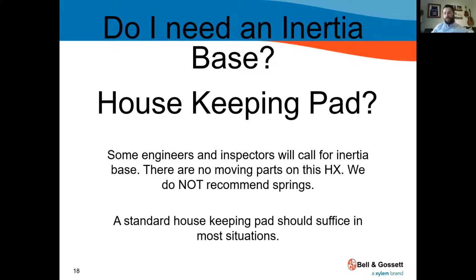There are no moving parts in the plate and frame heat exchanger. It's dumb equipment, if you will. There's no moving part. There's no rotating assembly. It shouldn't create a ton of motion except the water coming through on its own. So we don't recommend springs. You shouldn't need them. A standard housekeeping pad, usually 4 inches, should suffice in most situations.